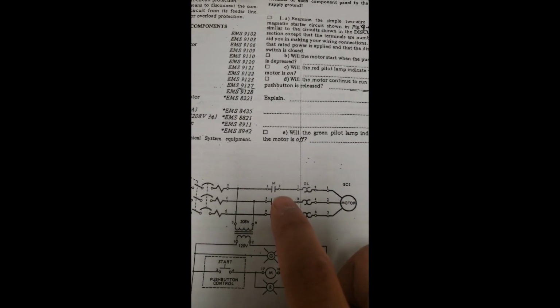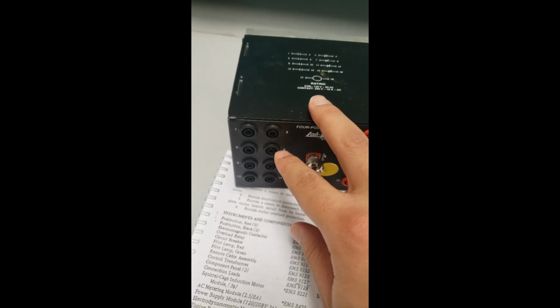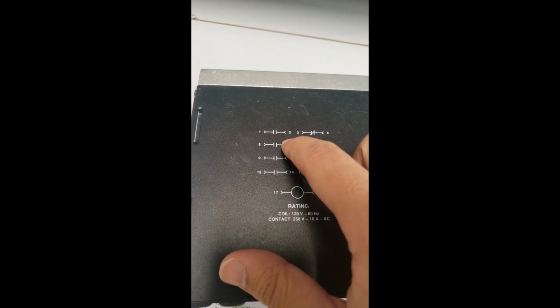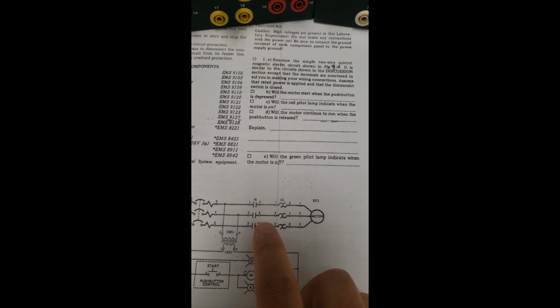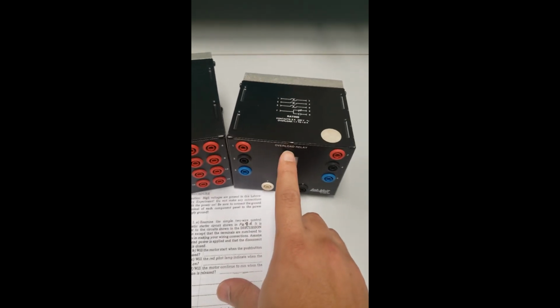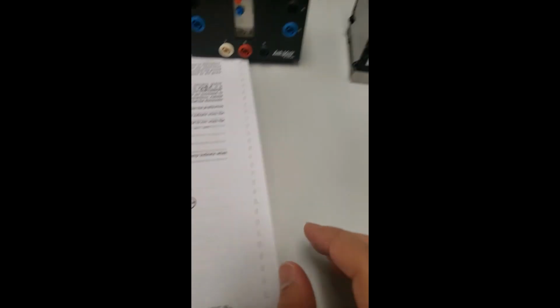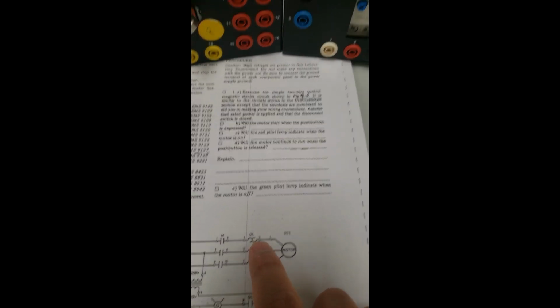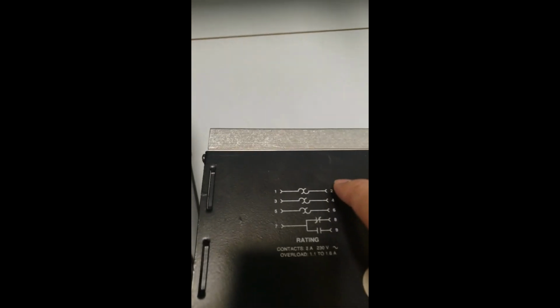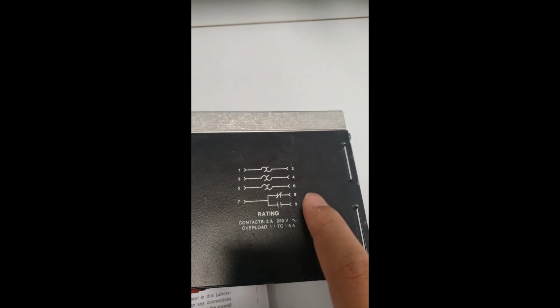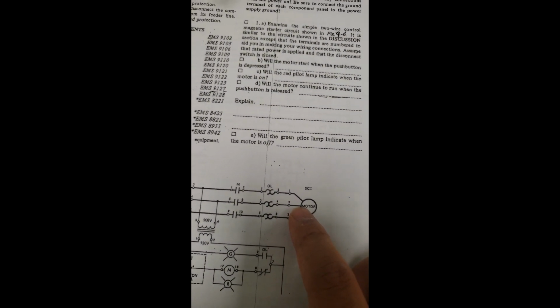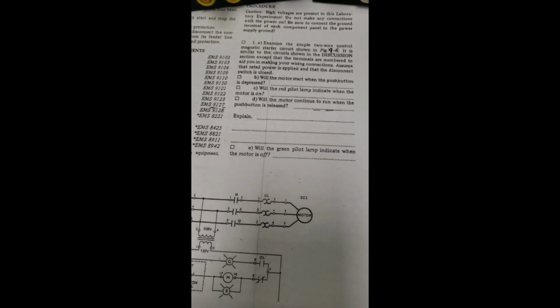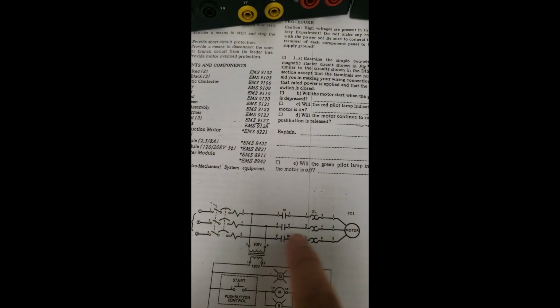Then from 2, 6, 10, which is this contact, to the overload relay, 1, 3, 5. 1, 3, 5 of the overload relay. Then out of the overload relay, you can see the contacts here, up. From 2, 4, 6 to the induction motor 1, 2, 3, which is the machine that we have. Now the power circuit is finished.